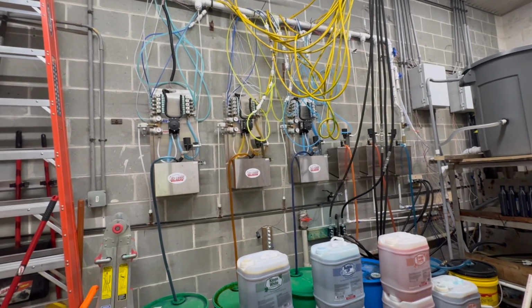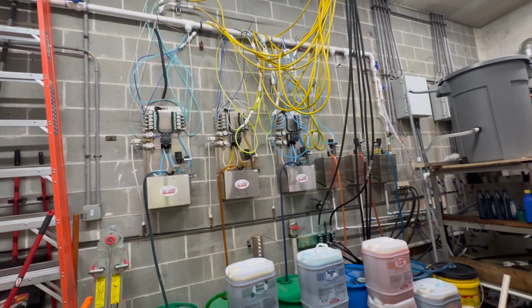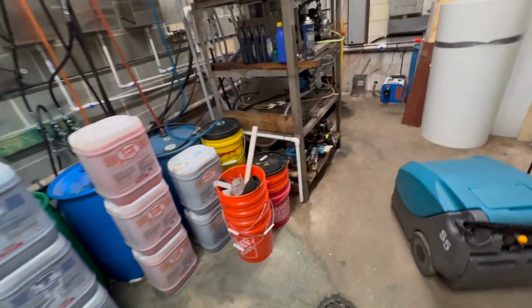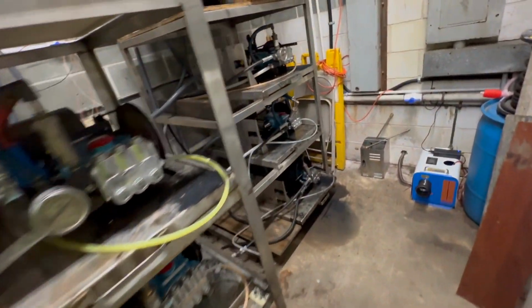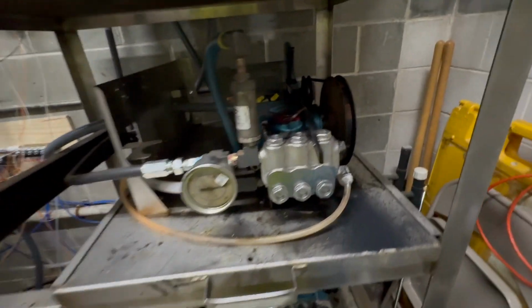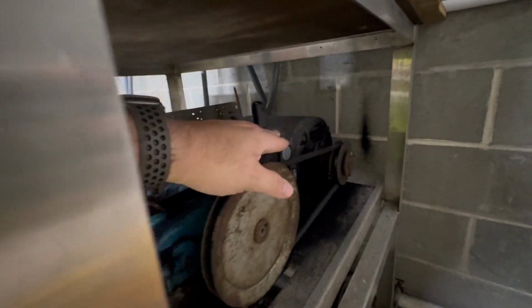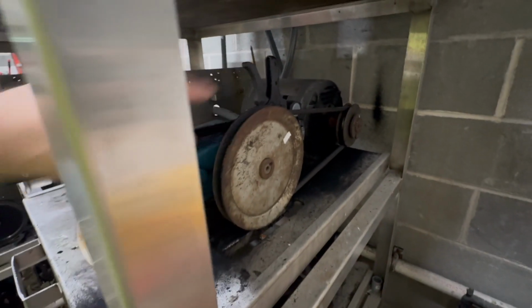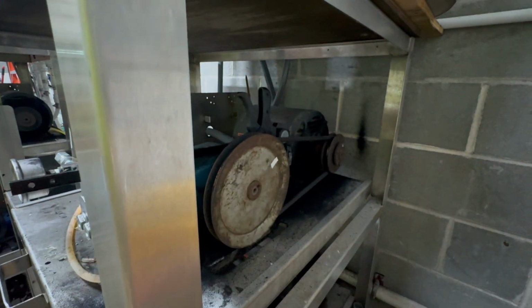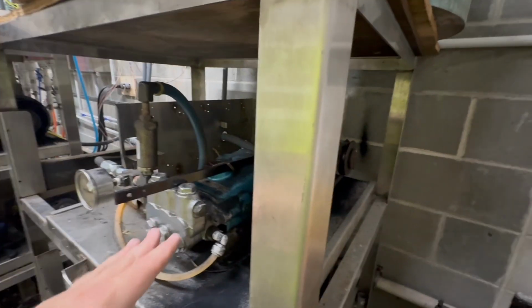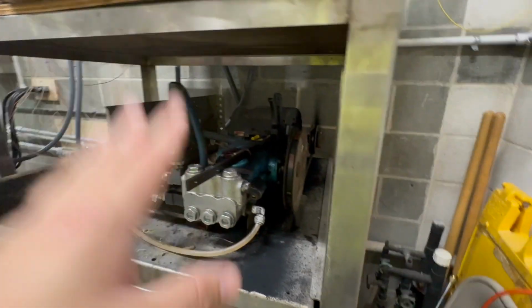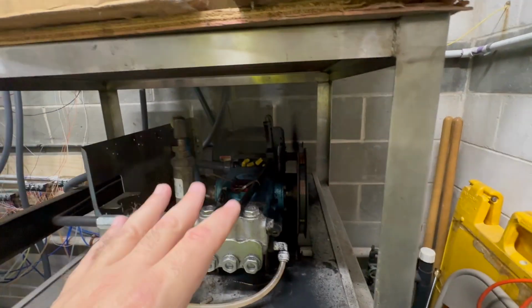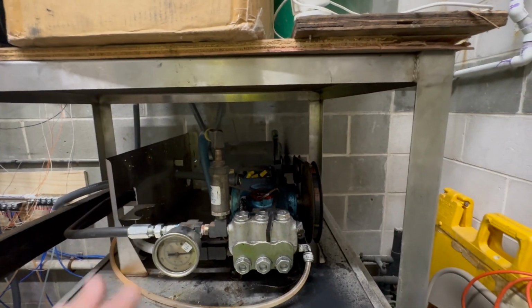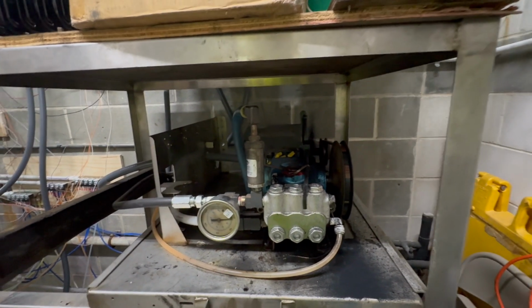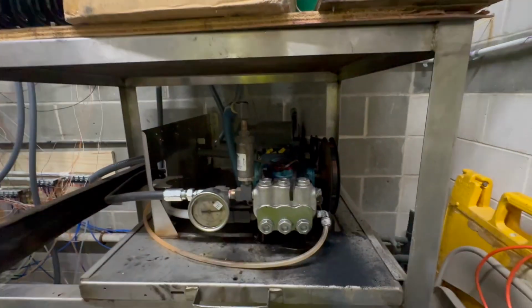So that's really very simple, the solution I have here. My pump setup is fairly simple, I'm running a belt drive to a 5-horse 3-phase motor, just a standard belt drive. The white mark is actually for a tachometer, because these need to run at 1,725 RPMs for optimal efficiency. If I start getting belt slippage, I can measure the speed the pump's actually turning at to make sure things are working. It requires some calculations because of the size of the pulley difference.